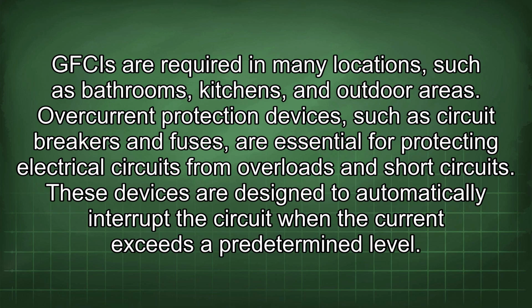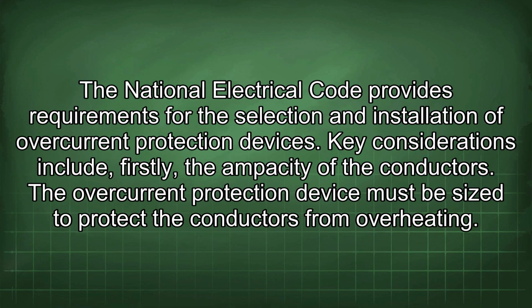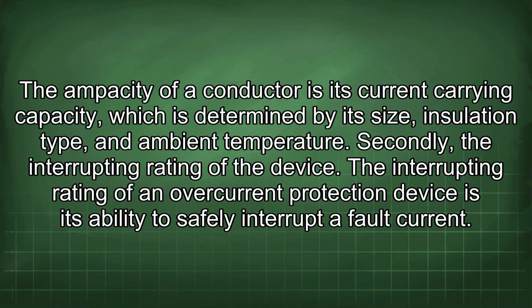Overcurrent protection devices, such as circuit breakers and fuses, are essential for protecting electrical circuits from overloads and short circuits. These devices are designed to automatically interrupt the circuit when the current exceeds a predetermined level. The National Electrical Code provides requirements for the selection and installation of overcurrent protection devices. Key considerations include, firstly, the ampacity of the conductors. The overcurrent protection device must be sized to protect the conductors from overheating. The ampacity of a conductor is its current carrying capacity, which is determined by its size, insulation type, and ambient temperature. Secondly, the interrupting rating of the device.